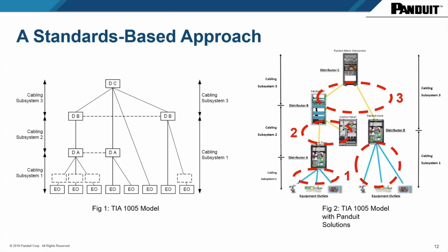Now we're talking about edge connectivity, where you have a category 3 for all of the M.I.C.E elements, to fiber that is now connecting above the subsystem 1. So anything from cabling subsystem 2 and 3 can now be running fiber between those devices. You could also run copper if these distances are not, like I said, over 100 meters. So in a small factory, you might decide to run copper throughout. But generally, we are on fiber between these enclosures.